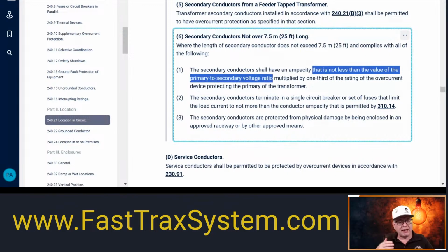We kind of did that in an example the other day. So in order to get the primary to secondary ratio, in this case, if it was a 75 kVA transformer and we have 480 primary and 208/120 secondary, typically delta primary, 208Y/120 secondary. In that scenario, the primary to secondary voltage ratio is just the primary divided by the secondary. So 480 divided by 208 gives me 2.307, and I can round this to 2.31. So that is the ratio we're working with.